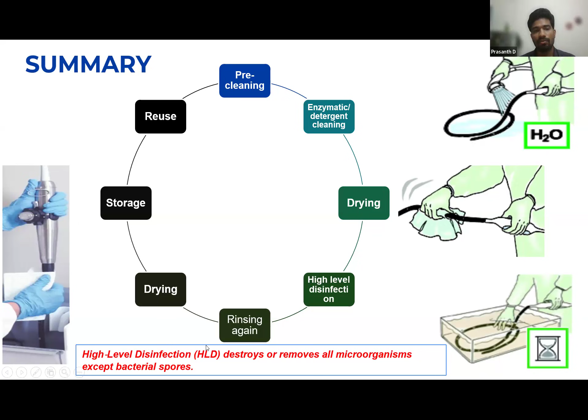The take home message is that the TEE probe must be cleaned after each and every use. Whenever removing it and introducing it into detergent or high level disinfectant, always use protective eyewear and gloves, and ensure detergent strength and duration of contact as specified by the manufacturer. Always use bite guards whenever the TEE probe is used. It should not be treated with autoclave, gas sterilization, steam or heat sterilization, gamma radiation, or bleach. It should be thoroughly dry before storing, and do not bend the shaft of the TEE probe into a circle with a diameter of less than 0.3 meter. The TEE probe should be articulated only with the controls, not with the hands. To check for motion, always use the wheels.